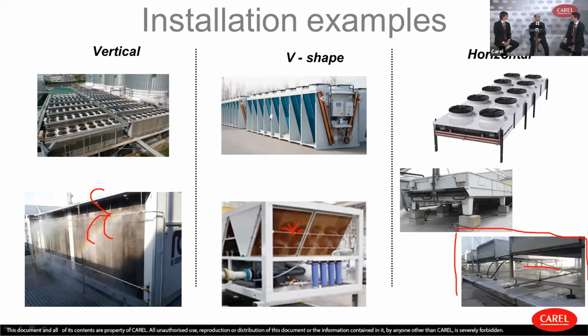I can envision that in the future, this dry cooler mode with water feeding several small chillers could be a model. It's a way to reduce the refrigerant charge, so the chiller is more compact and it's water condensed, but by means of having the evaporative cooling, you could really reach outstanding efficiencies.